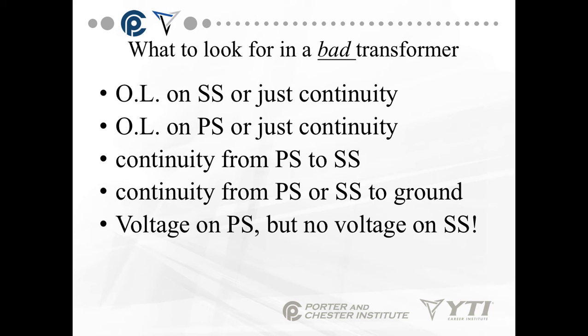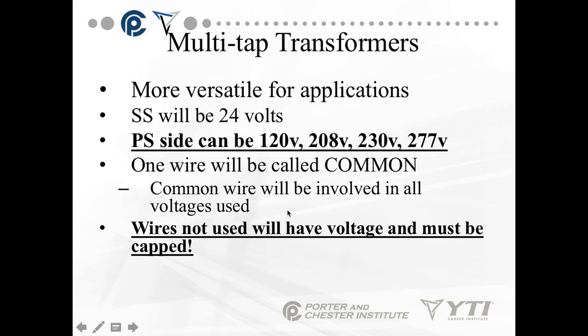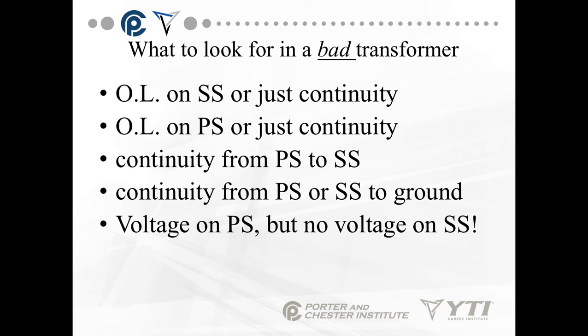What we're looking for on a bad transformer: OL or infinite on the secondary side, OL on the primary side, continuity from PS to SS, which is primary to secondary, continuity from primary side or secondary side to ground, or voltage on the primary side but no voltage on the secondary side. And I'm going to tell you this last one is what you are going to have most often.